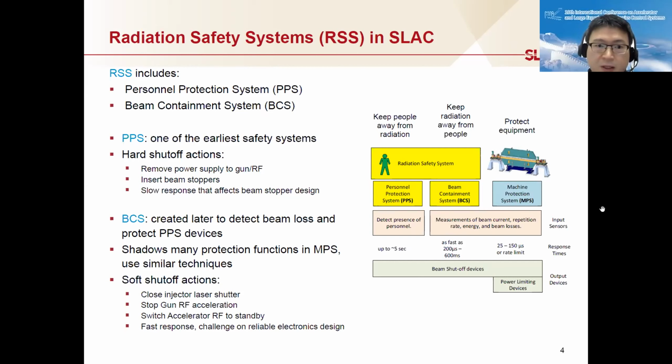The PPS is the earliest system designed at SLAC. It's a hard shutoff, meaning we remove the power supply to the gun and RF, and we insert beam stoppers downstream. Overall, the response time is pretty slow. Our design is around 5 seconds.